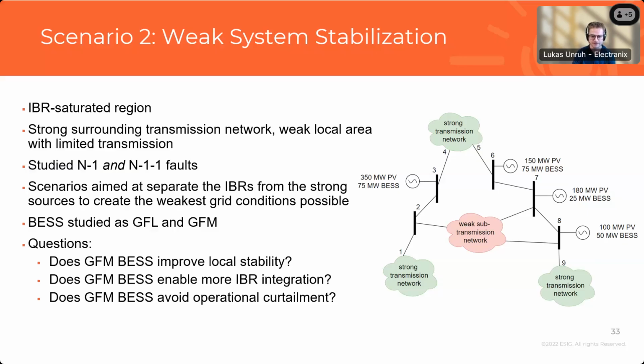And yeah, so this is a fairly IBR saturated region. Once we take out some of these lines or WSCRs or SCRs, they drop below 2 relatively quickly. And similar to the strong system case, we had our baseline scenario, which consisted of the batteries as grid following. And then we substituted those out for grid forming batteries.